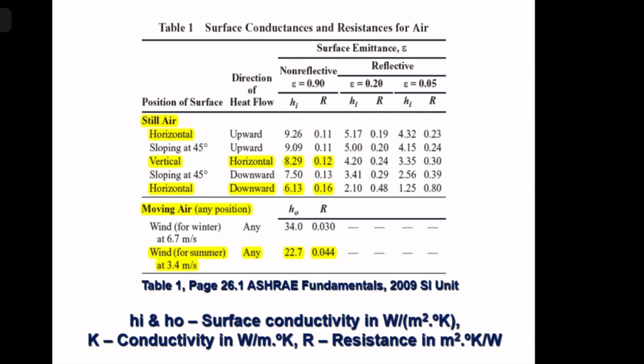Similarly, for outside air, they have considered two wind velocities. One is a little windy condition, 6.7 meter per second. Another is a little not windy condition, 3.4 meter per second. So I have considered 3.4 meter per second outside wind velocity. There, the R value for the outside still air is 0.04. I have also given the reference, page number 26.1, ASHRAE Fundamentals. This is a little old, 2009 edition, but I think this has not changed over the years.